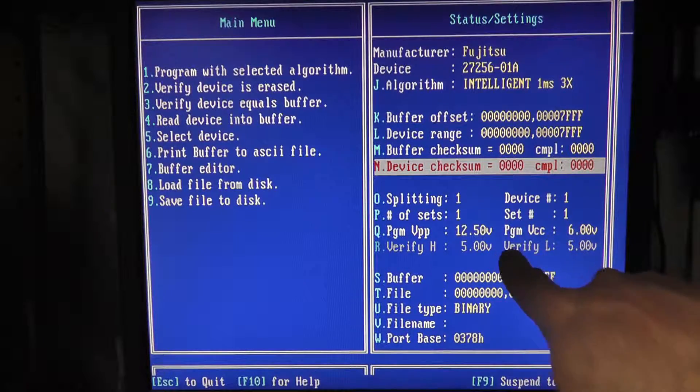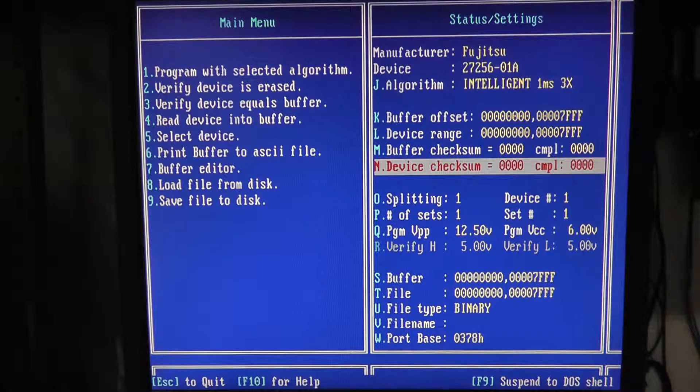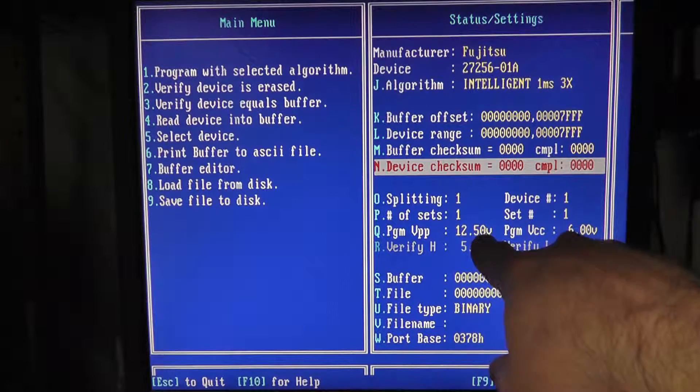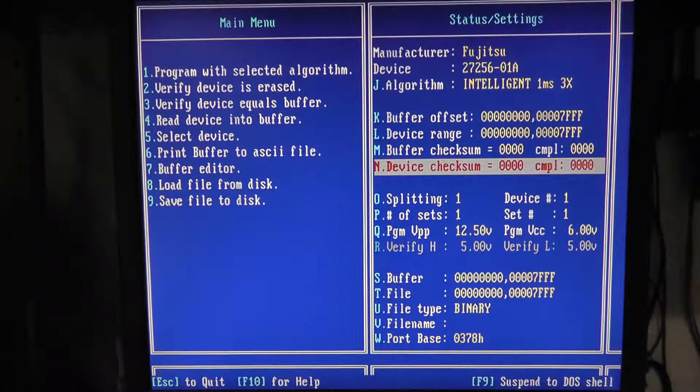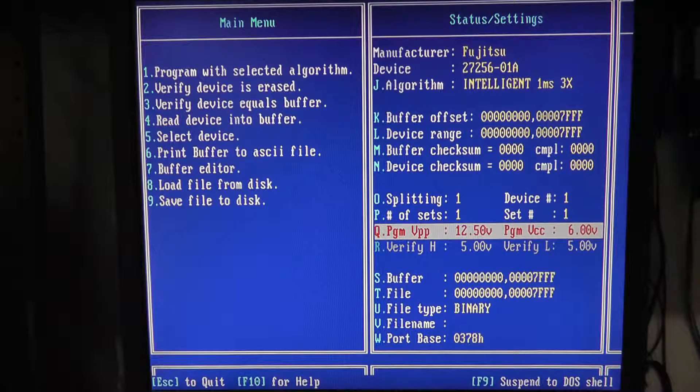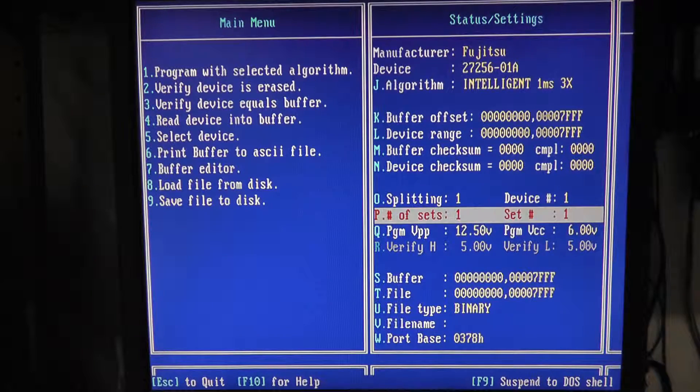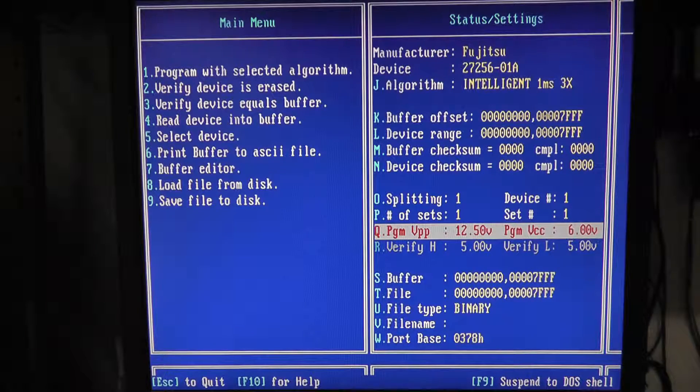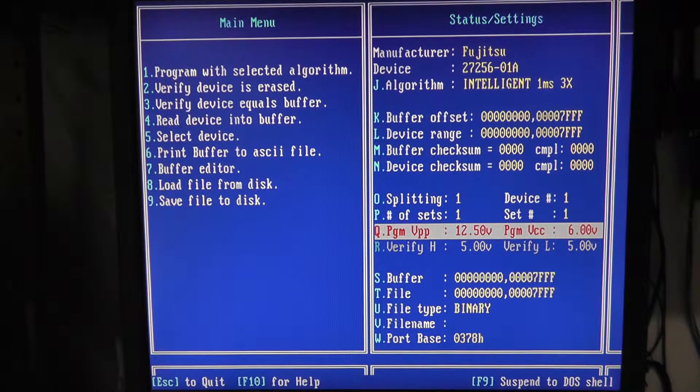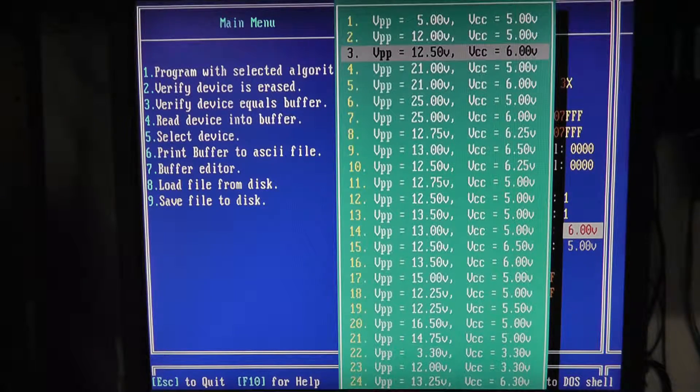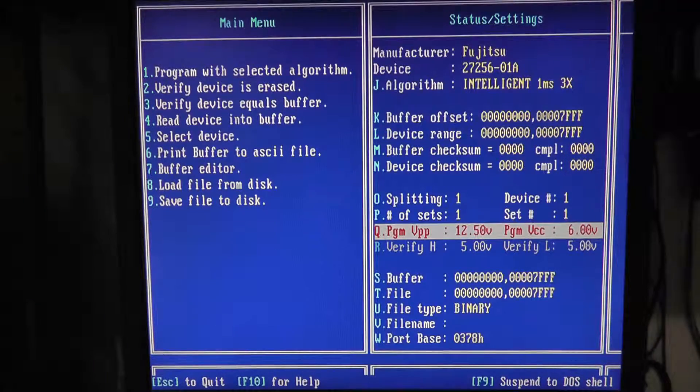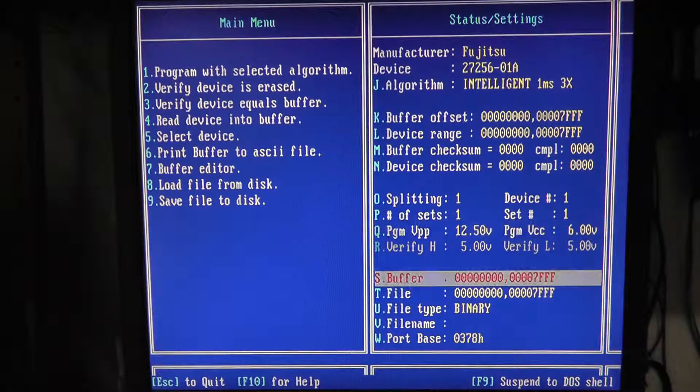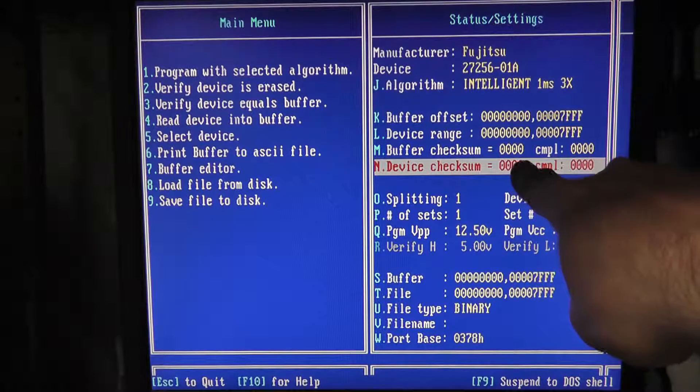Okay, so I did check the data sheet and so this is a plus mark for the EMP devices. 12.5 volts is the correct voltage. I'm going to go back and look at the ROM max here in a second, but I could have swore it said 21 volts and I didn't check the data sheet. So it's smart to, you're trusting that they programmed it correctly. The nice thing is we could come in here and actually manually change that, which I also like, because maybe they did have it wrong and we could do that.